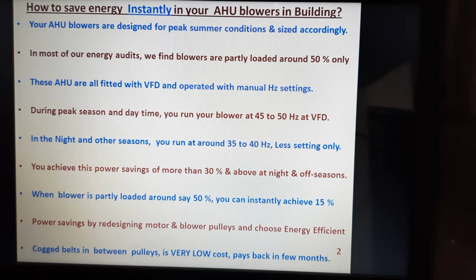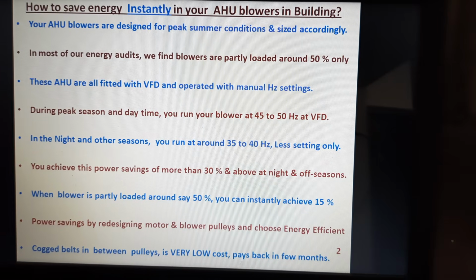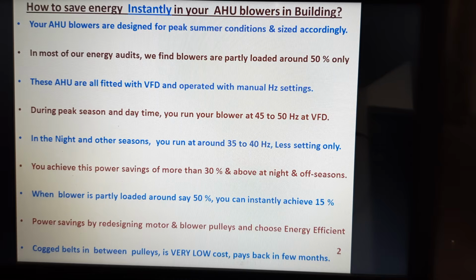During the peak season and in the daytime, you run your blower at 45 to 50 Hz on the VFD. At night and in other seasons, you run at 35 to 40 Hz, by hertz setting only. So you can achieve power savings of around 30%, which you are already achieving during the night and in the off seasons. So when the blower is partly loaded at around 50%, you can still achieve another 15% instantly by redesigning the motor and blower pulleys and choosing energy efficient cogged belts between the motor and blower pulleys. This is very low cost and the payback is in a few months.